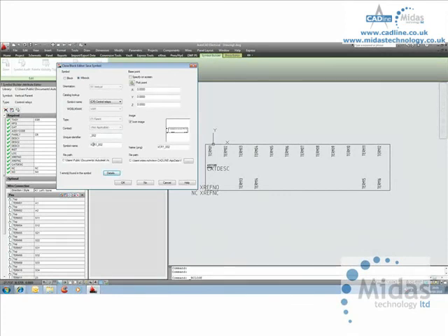It is a vertical, we'll define it as a control relay. It's a parent, which is why the first four characters, so vertical is V, H for horizontal, CR for control relay. That looks in the parts database for control relays, which are the PILTs are in that section. One for a parent, two for a child, whatever you want to call it thereafter, entirely up to you. Obviously you can create an icon image, which means it goes into the library. We want to W block it, so it saves it into the library as well. I say OK.